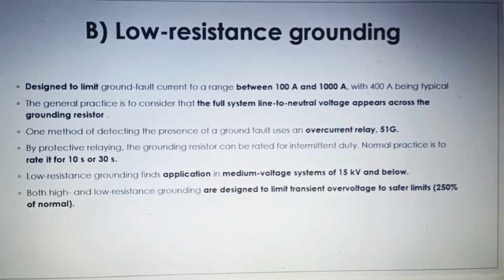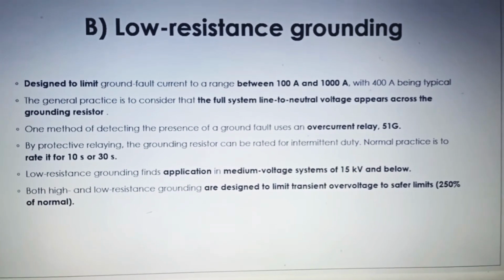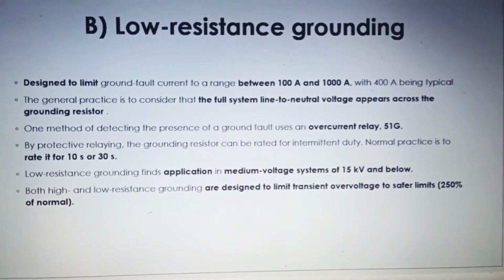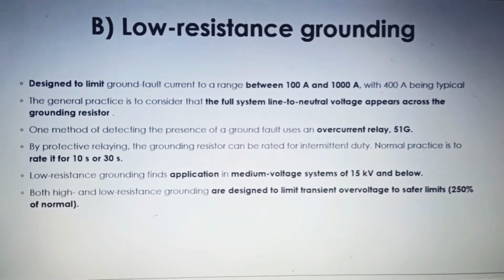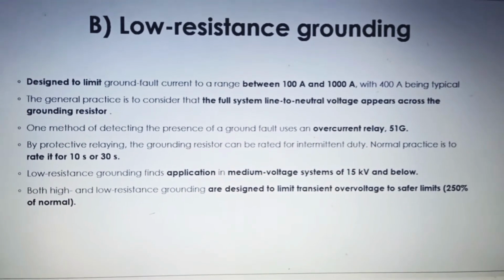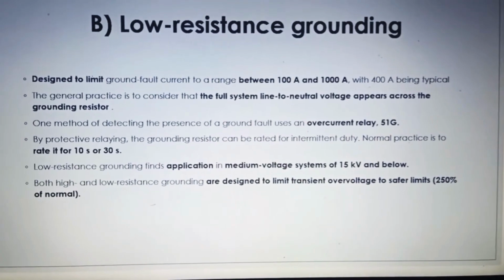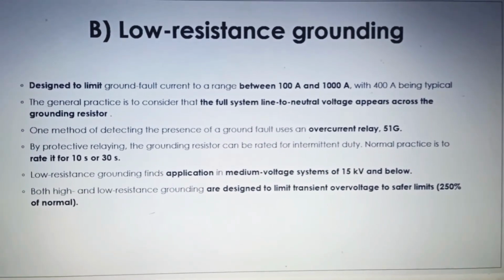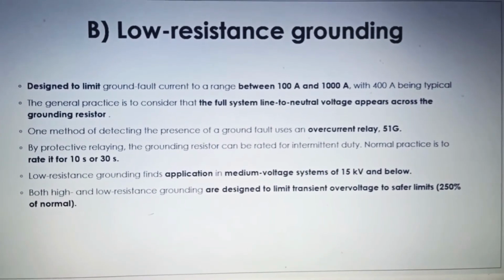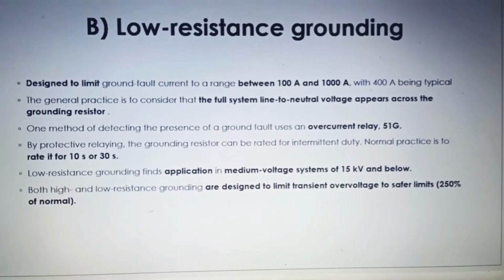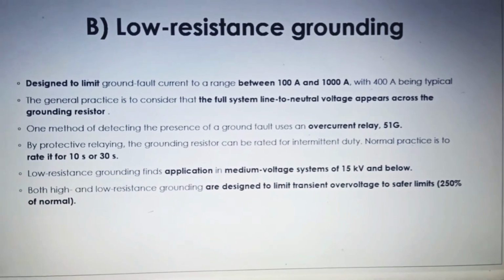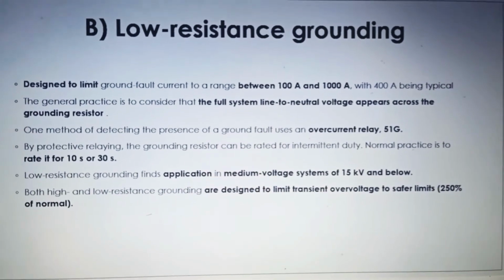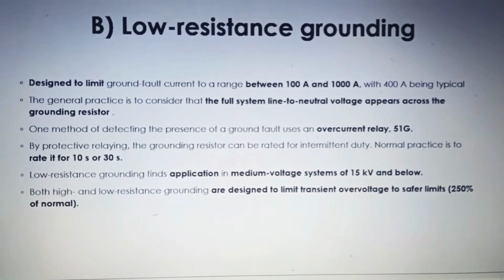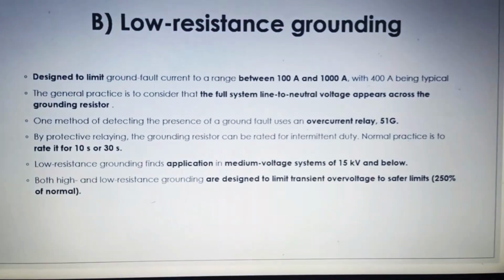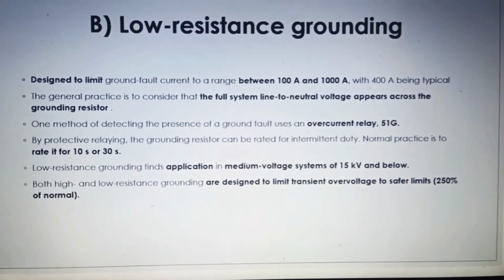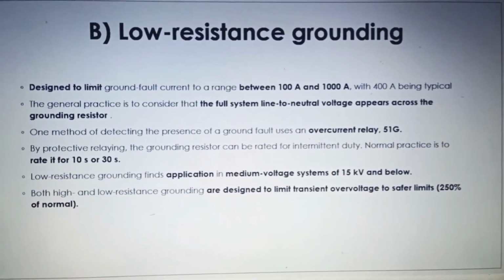One method of detecting the presence of ground fault is by using overcurrent relay 51G. In this method, when a ground fault occurs, the neutral potential is raised to approximately line-to-neutral voltage, resulting in a current flow through the resistor. A typical turn ratio for the current transformer is indicated. Upon indication that a ground fault current has occurred, action would be initiated to disconnect the transformer from the secondary circuit.